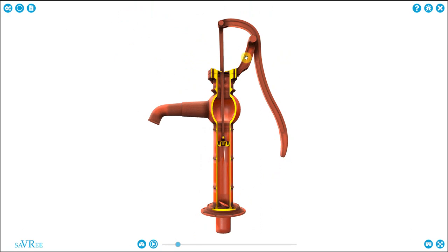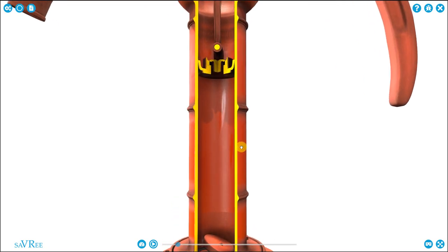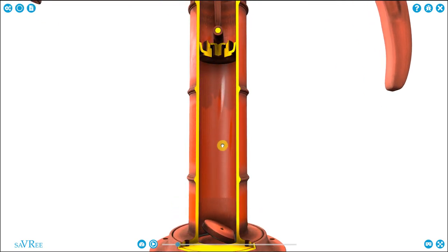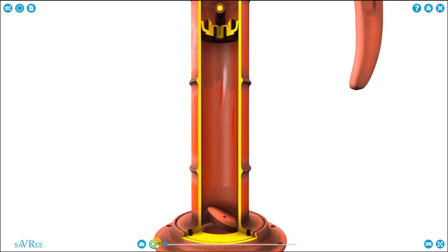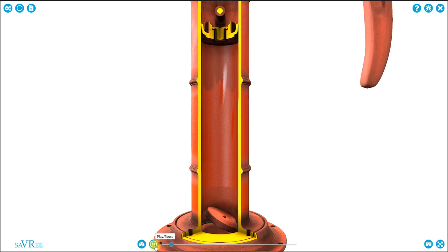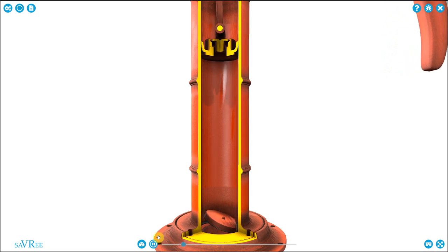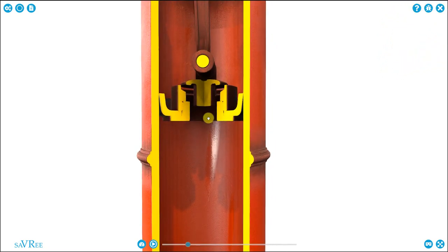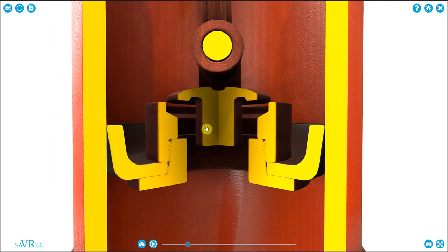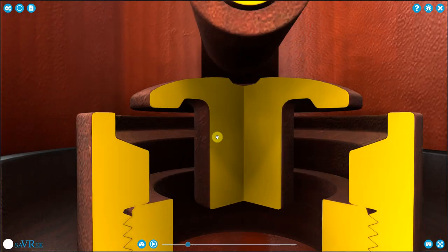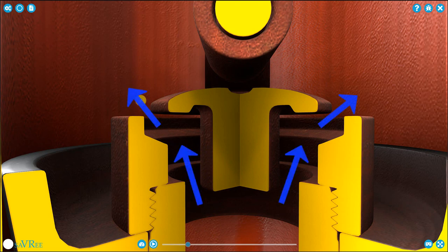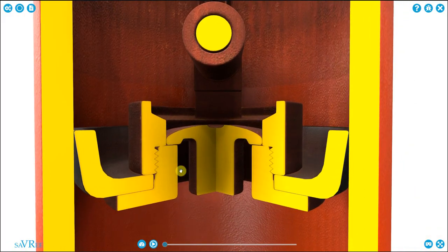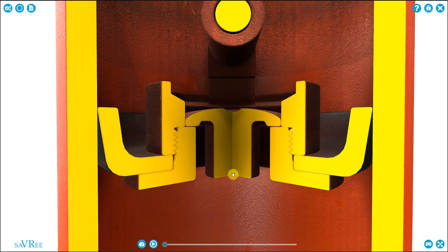Let's ignore the handle or the lever for a moment. And just zoom in and have a look at the foot valve and our piston valve. I'm going to slow the animation down. The piston is going to start at the top and move its way downwards. So the piston is now moving down. Notice that our foot valve is closing. And notice that the gap here between our piston valve or the disc of our piston valve and the seat has increased. It hasn't actually increased. What's actually happened is that there is now a gap. Whereas before there was no gap. This means that fluid will be able to pass up from the bottom to the top. It's going to come up along here. If we go back to the top, you'll see that here the disc is pressed against the seat and the valve is closed.